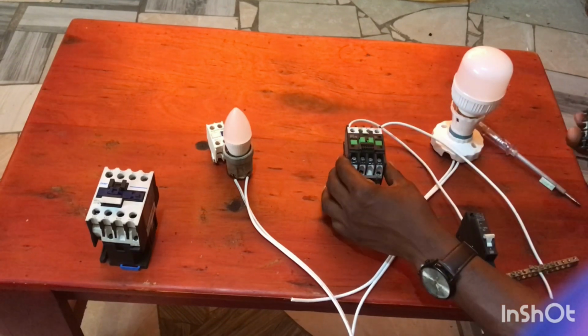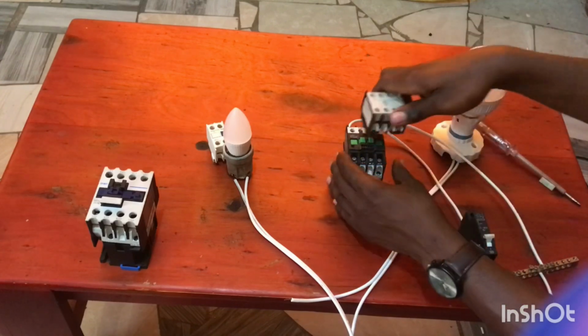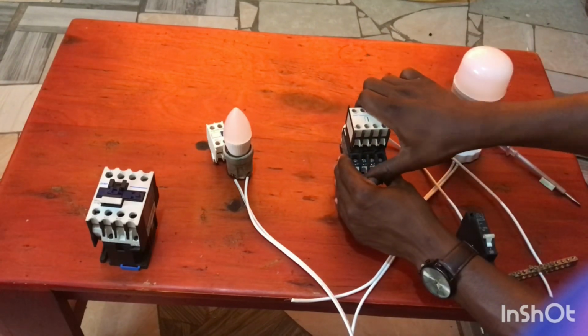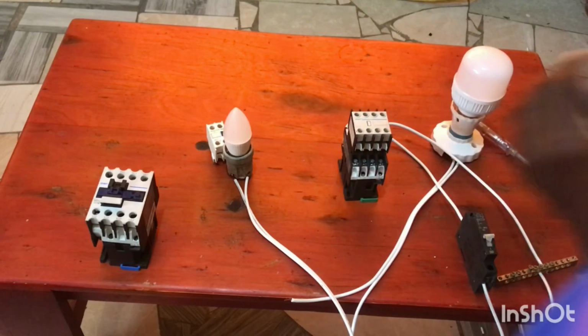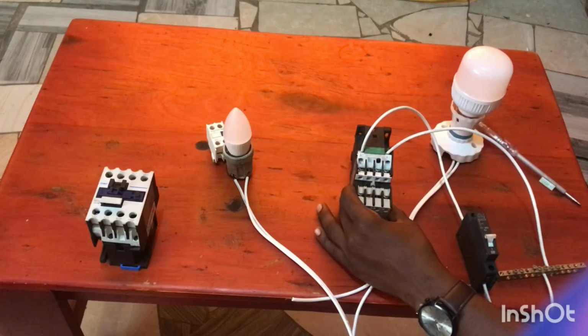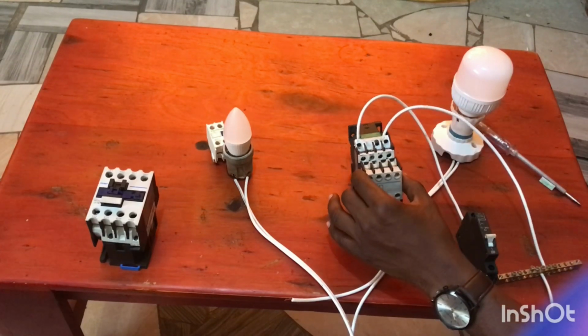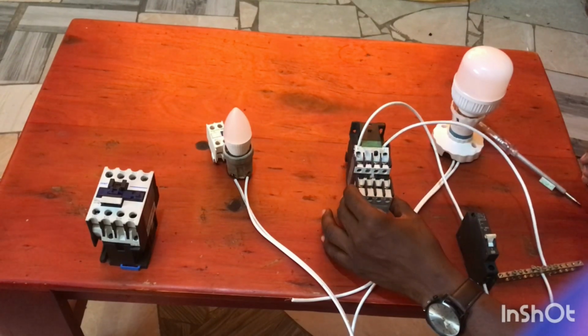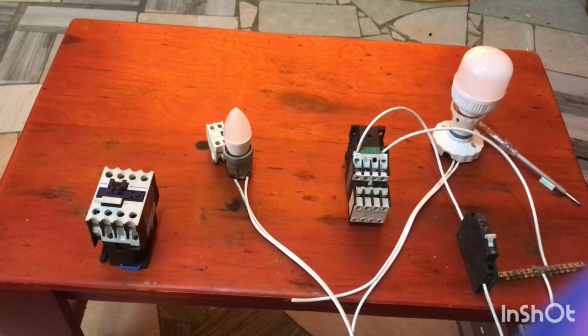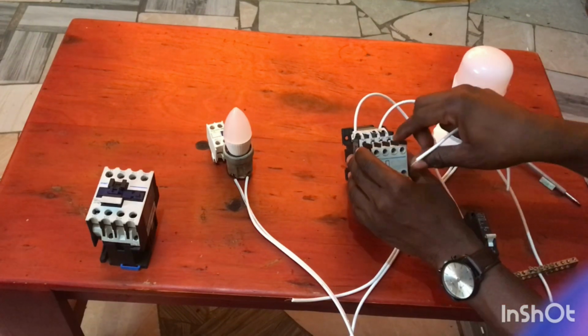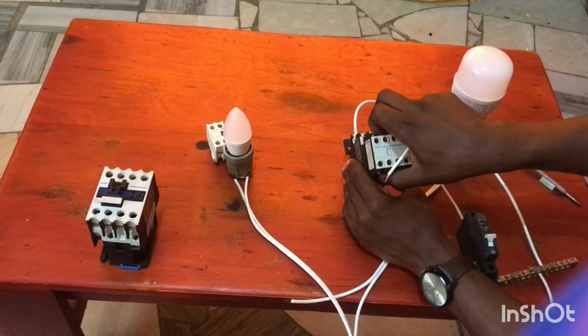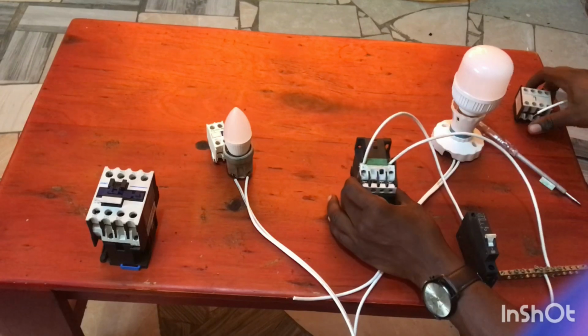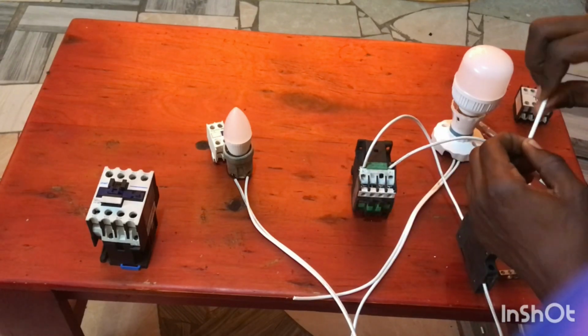As I explained, an auxiliary relay is a combination of normally open and normally closed. A contactor only has normally open, but for us to have a normally closed contact, we'll have to put an auxiliary relay so as to increase the chances of making an automatic switch for an appliance that we want to switch on automatically.